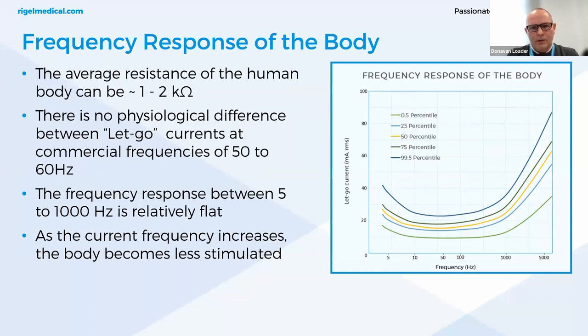The average resistance of the human body can be 1 to 2 kilohms. There is no physiological difference between let-go currents at commercial frequencies of 50 to 60 hertz — the impact to the human body is the same in this range. The frequency response between 5 and 1,000 hertz is relatively flat, causing the same sort of effect. As current frequency increases, the body becomes less stimulated. The results from exposure are dependent on the amount of current delivered and vary from slight perception to severe burns and ventricular fibrillation.